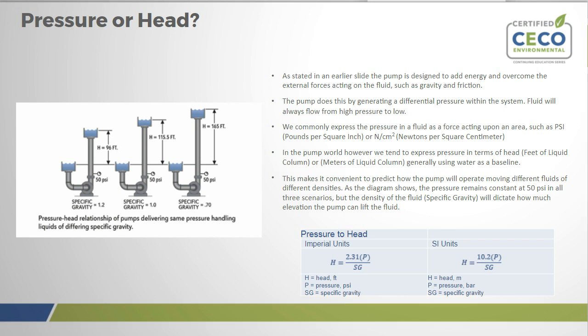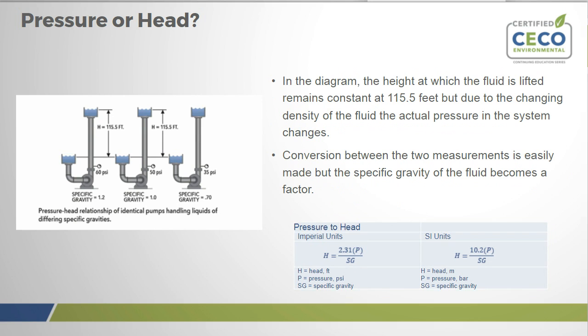Conversely, the same is true for pumping. We can pump to the same height, and you will notice that the actual pressure that is recorded on your gauges will be different. In the diagram below, you see that you're pumping to 115.5 feet, and that remains constant throughout. But because the specific gravity is changing from 1.2 to 0.7, the pressure in the lines and the pressure that you will read on your gauge will actually be significantly different. In the first case, 60 psi, 50 psi, and 35 psi, respectively.